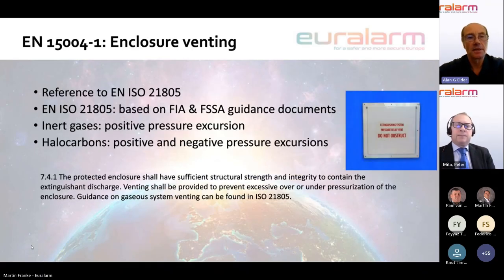Martin, please. So the next one is a topic very familiar to the industry, and this is the one of enclosure venting. It's well known that when you discharge a volume of gas into a protected enclosure, depending on the gas tightness of the enclosure, you will experience varying levels of pressure within the space. The inert gases exhibit a positive pressure excursion, and with the halocarbons, you will get both a positive and a negative pressure change within the space.